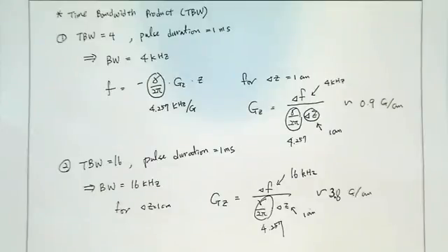So there is always a trade-off in RF excitation pulse design. You have to understand your hardware limitation, which is the gradient as well as B1 amplitude, and your physiological limitation, somewhat related to the pulse duration. For a given pulse duration that you can allow, and a given hardware limitation like gradient amplitude and B1 amplitude, you can maximize your time bandwidth product to have a better slice profile. Okay? That's the way you think about how to design the RF pulse.